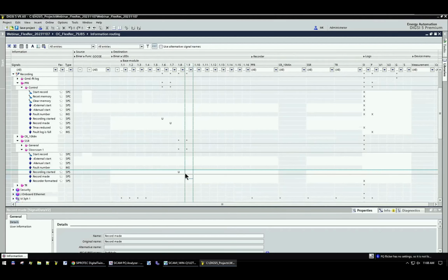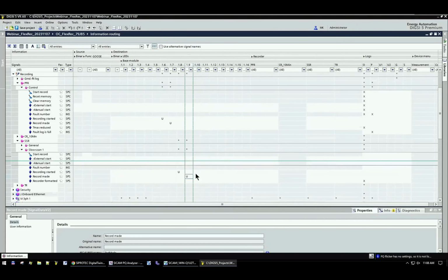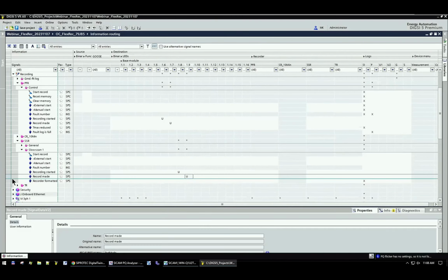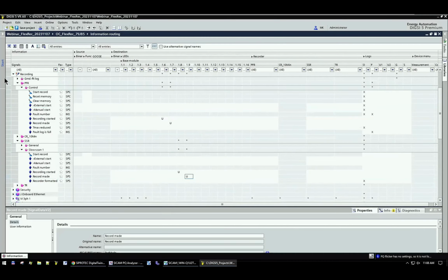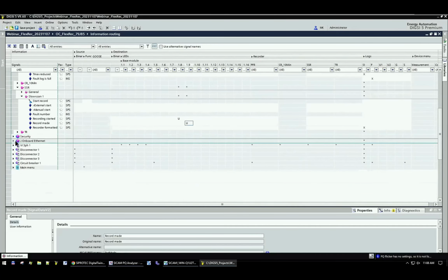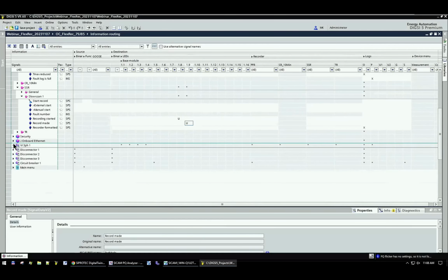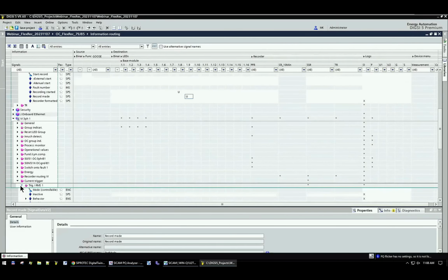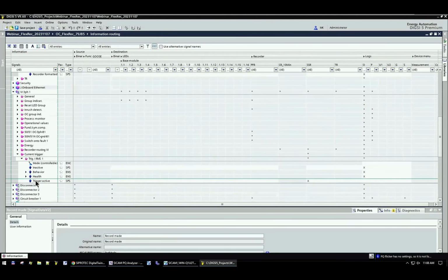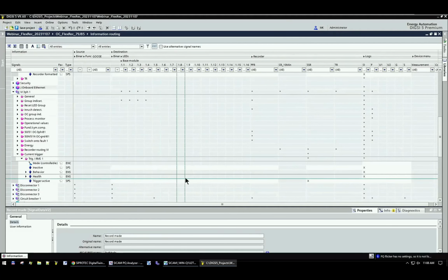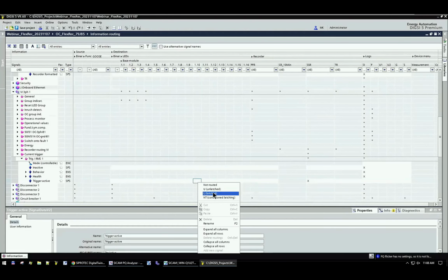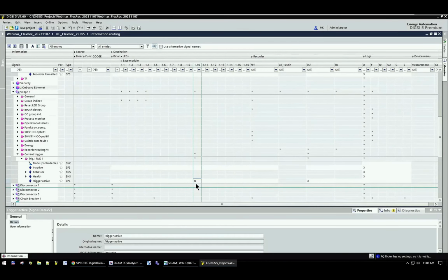Okay. So LED number 10 on the base module, I will use for our current trigger. Where is our current trigger? Our current trigger is in the voltage current three-phase function group. Close to the end, current trigger. And when this trigger becomes active, here one, trigger active, I would like to assign this to LED number 10 on the front panel. Here we are. Okay.